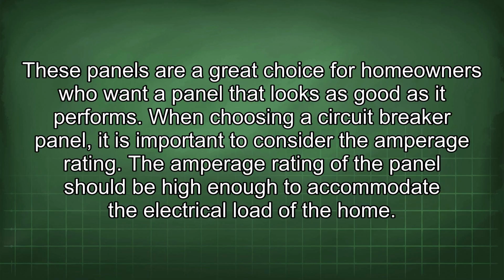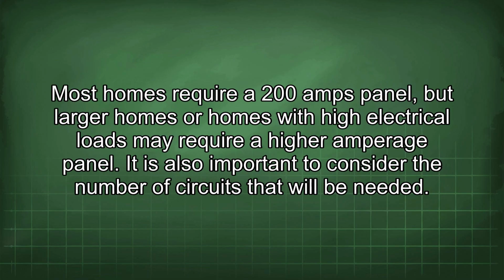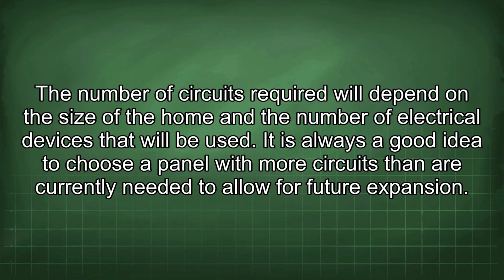When choosing a circuit breaker panel, it is important to consider the amperage rating. The amperage rating should be high enough to accommodate the electrical load of the home. Most homes require a 200 amp panel, but larger homes or homes with high electrical loads may require a higher amperage panel. It is also important to consider the number of circuits needed, which depends on the size of the home and the number of electrical devices used. It is always a good idea to choose a panel with more circuits than currently needed to allow for future expansion.